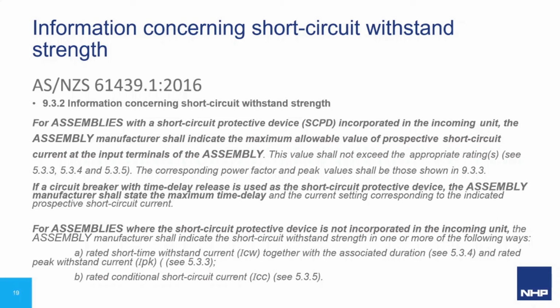For assemblies where the short circuit protective device is not incorporated in the incoming unit, or the protective device is in the upstream assembly, as is commonly the case, the assembly manufacturer can indicate the short circuit withstand strength in one of the following ways. The first option here is a rated short time withstand current, or an ICW, along with the rated peak withstand current, IPEAK. ICW is usually the most flexible for the system designer, as they can use the ICW and IPEAK ratings to do their own calculations and nominate appropriate upstream protection.